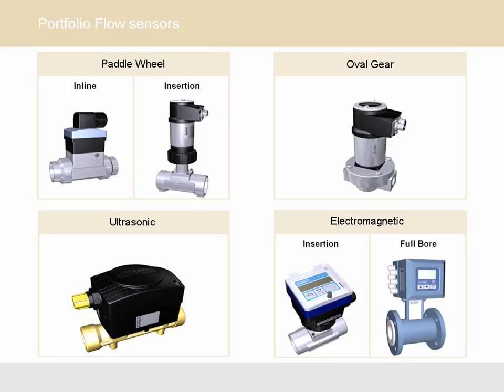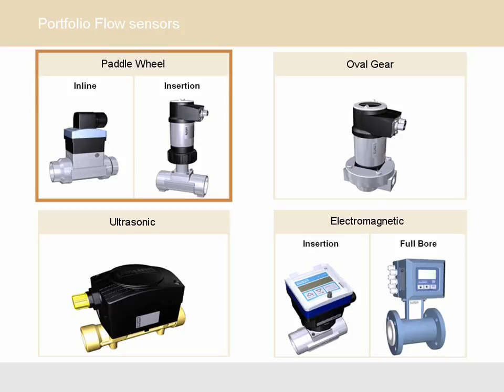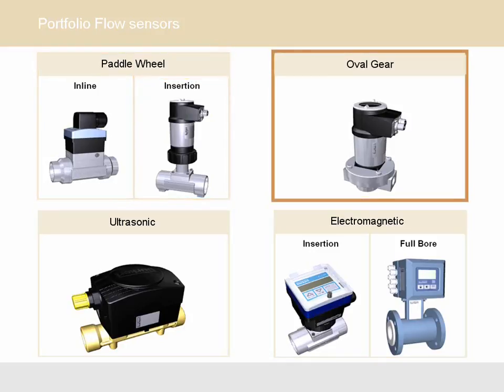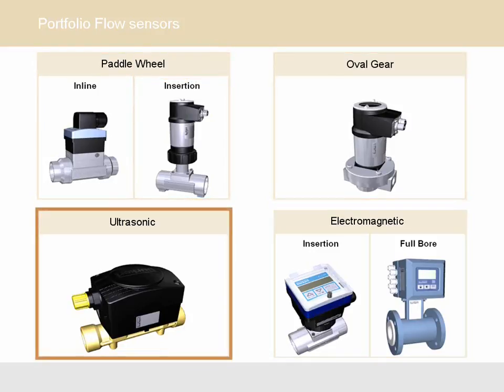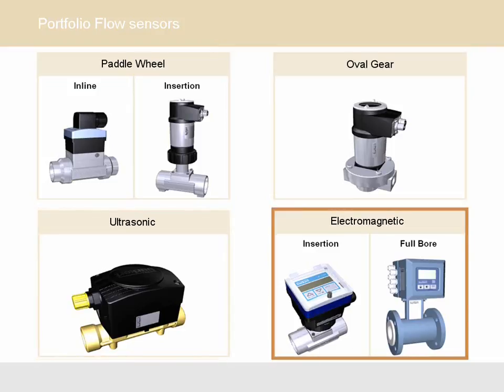What about the product portfolio for flow measurement? Flow measurement at Bürkert includes sensors with several different measuring principles. The paddle wheel, of which there are two design lines, inline and insertion. The oval gear. And ultrasonic and electromagnetic inductive flow measurement, in short, EMF. These flow meters are subdivided into two lines, insertion and full bore.